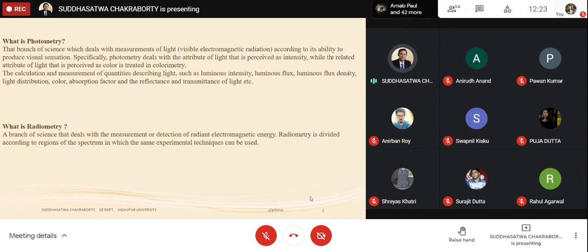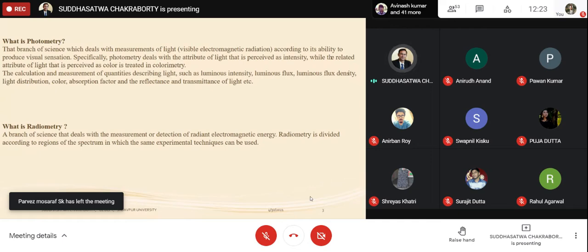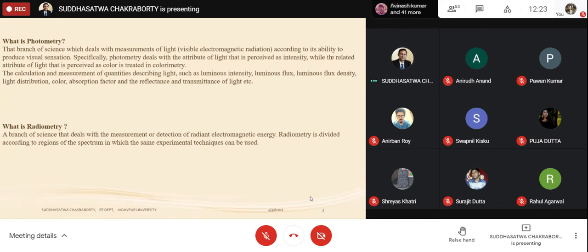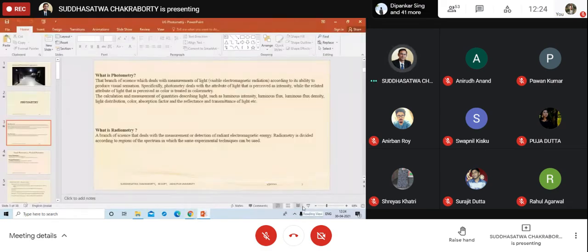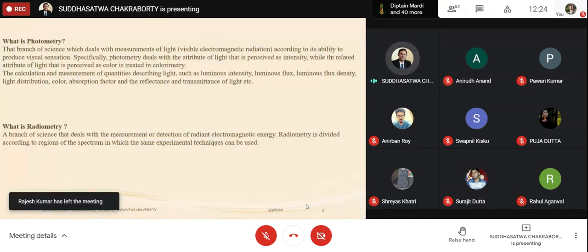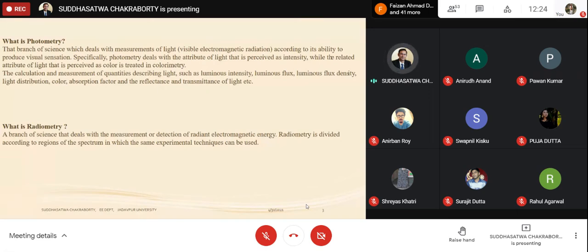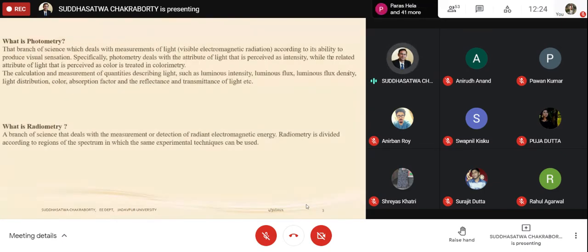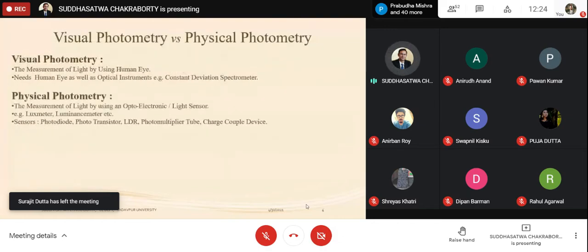Radiometry uses a sensor not confined to measuring only visible light. CCD is a very good source for radiometric measurements. If measurement is confined within visible light, it's photometry; if it goes beyond that — infrared or ultraviolet — it's radiometry. In our laboratory we have UV-A, UV-B, and UV-C dedicated sensors, which are radiometric devices measuring equivalent parameters to those in photometry.